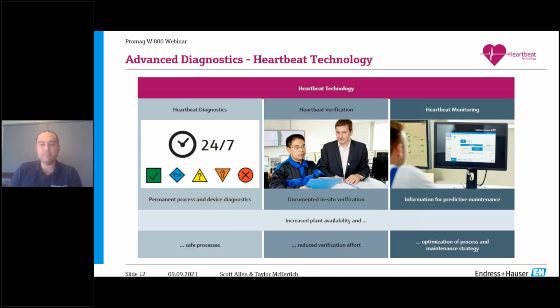The verification piece is a guided procedure for testing and health checking, with a fully traceable, documented certificate saying whether the meter is in good working order or not. This references diagnostic values, checking threshold values, and then passing or failing a meter. We have an example later to show you how that looks.